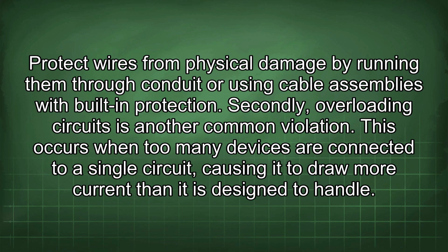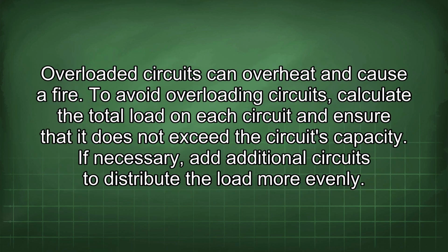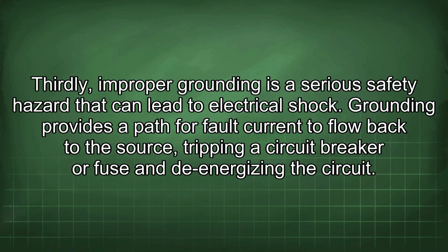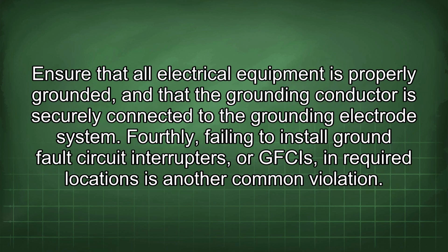This occurs when too many devices are connected to a single circuit, causing it to draw more current than it is designed to handle. Overloaded circuits can overheat and cause a fire. To avoid overloading circuits, calculate the total load on each circuit and ensure that it does not exceed the circuit's capacity. If necessary, add additional circuits to distribute the load more evenly. Thirdly, improper grounding is a serious safety hazard that can lead to electrical shock. Grounding provides a path for fault current to flow back to the source, tripping a circuit breaker or fuse and de-energizing the circuits.